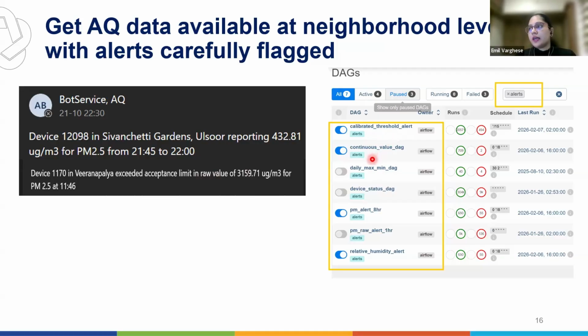Or sometimes a sensor goes bad and just continuously gives you the same data — say a CO value of 2 ppm received every day, continuously, every minute, the data just comes as CO 2 ppm. This means there's no change in the data throughout the day, so you can look into that as well.